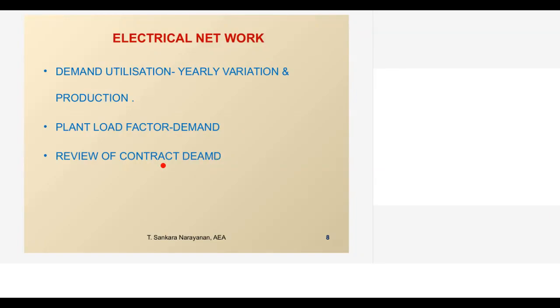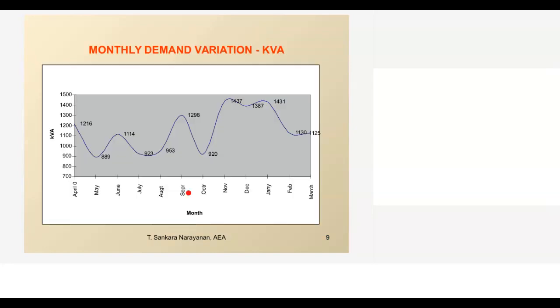But for some government sector organizations like ports, if there is a demand increase, the utility will allow it because they are a critical industry. So we have to review based on the site condition which demand we have to review. This is a case of one of the engineering industries. We have plotted for 1 year what the demand variation is. If you go through this, the plant can operate from 890 kVA up to 1400 kVA.